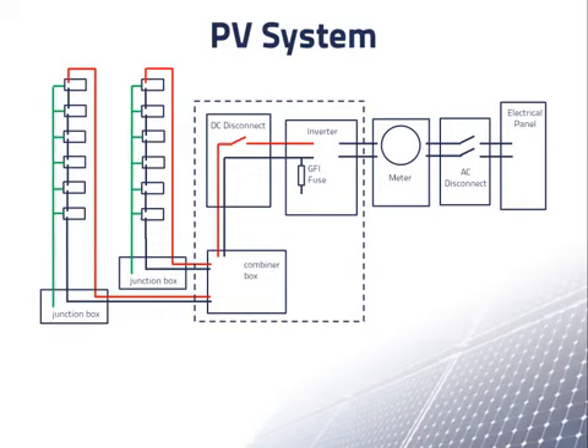From the junction boxes, the equipment grounding conductors go to the combiner box, where they can merge and then onto the DC disconnect and the inverter. If the enclosures of the combiner box and the DC disconnect are metal, then they need to be connected to the equipment grounding conductor, as shown here. We refer to the ground in the DC part of the PV system as the DC ground.